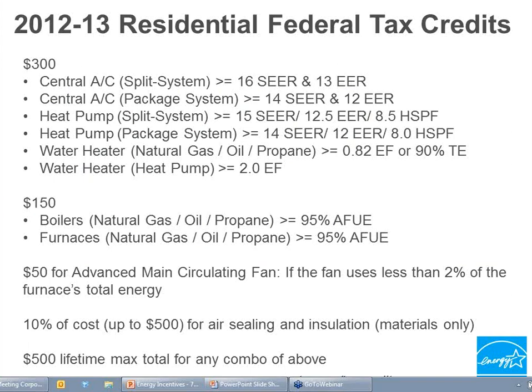So the main ones that you would normally pay attention to for split system central AC have to be 16 SEER and 13 EER. It has to be both. It's not an either-or. It's both you have to hit. For boilers and furnaces, you have to be 95% AFUE.